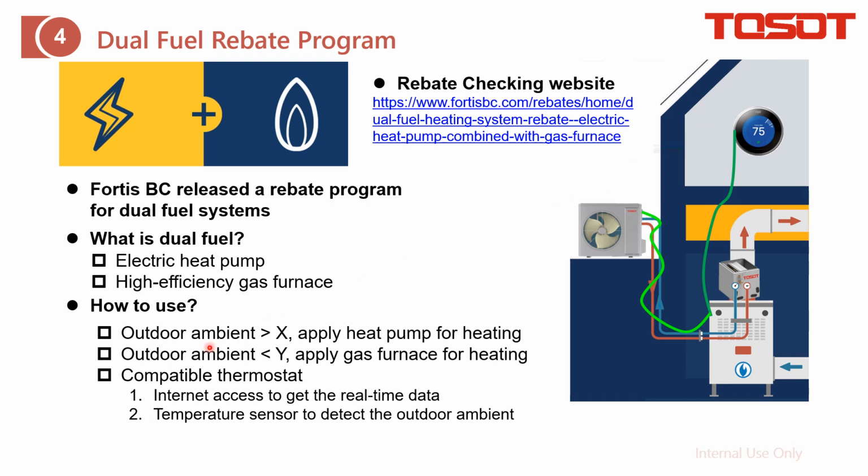So the next question is how to use it. It depends on the outdoor ambient. If it is higher than, let's say, 5 degrees, then we will apply the heat pump for the heating. At that period, the heat pump is still very powerful. It can cover all the heating required from the indoor.